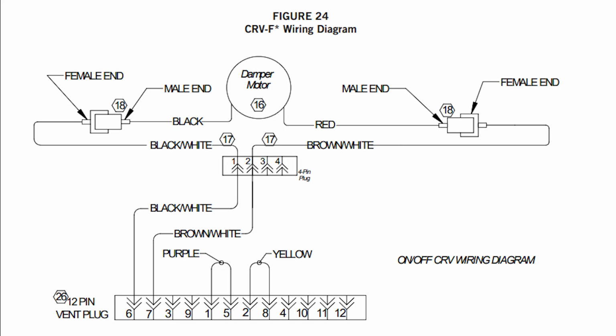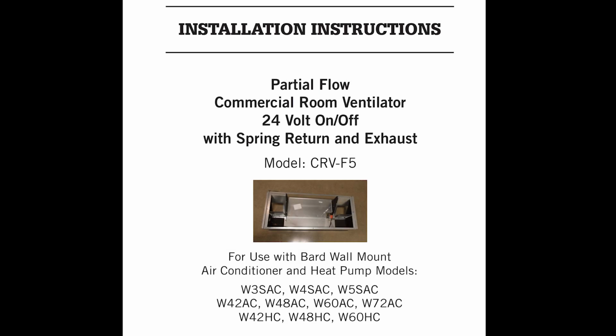This CRV does not have a control board, but rather a direct 24-volt AC connection to the actuator motor energized at the low voltage terminal A. We will start with the basic non-CO2 sensor controlled method. Use the flow charts from document 2100-751 on pages 9 through 13 for your specific unit model number.